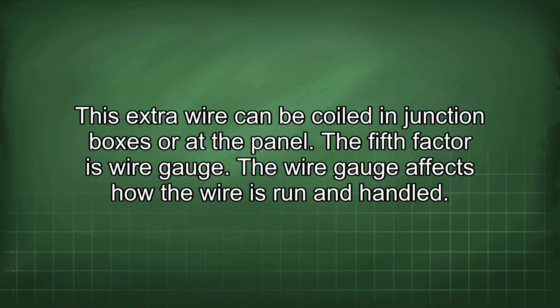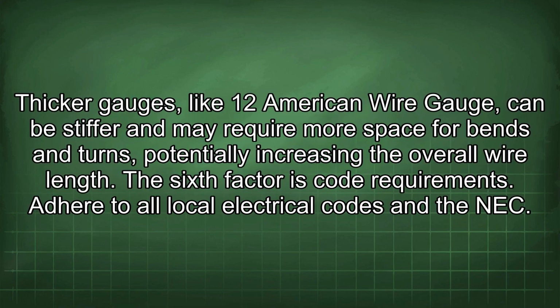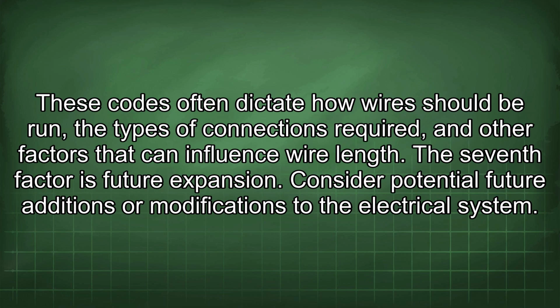The fifth factor is wire gauge. The wire gauge affects how the wire is run and handled. Thicker gauges, like 12 American wire gauge, can be stiffer and may require more space for bends and turns, potentially increasing the overall wire length. The sixth factor is code requirements. Adhere to all local electrical codes and the NEC. These codes often dictate how wires should be run, the types of connections required, and other factors that can influence wire length.